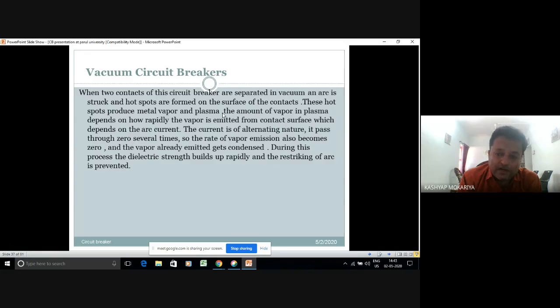The current is alternating in nature, it passes through zero several times, so the rate of vapor emission also becomes zero, and the vapor already emitted gets condensed. During this process, the dielectric strength builds up rapidly and restriking of the arc is prevented. So all these things are very important.